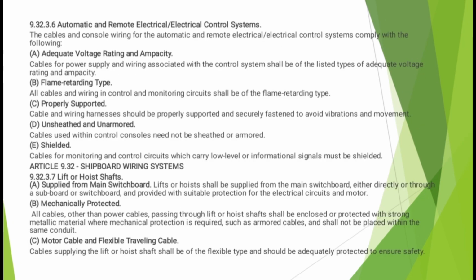Automatic and remote electrical control system. The cables and console wiring for the automatic and remote electrical control system comply with the following. Adequate voltage rating and ampacity. Cable for power supply and wiring associated with the control system shall be of the listed types of adequate voltage rating and ampacity. Flame retarding type. All cables and wirings in control and monitoring circuit shall be of the flame retarding type.